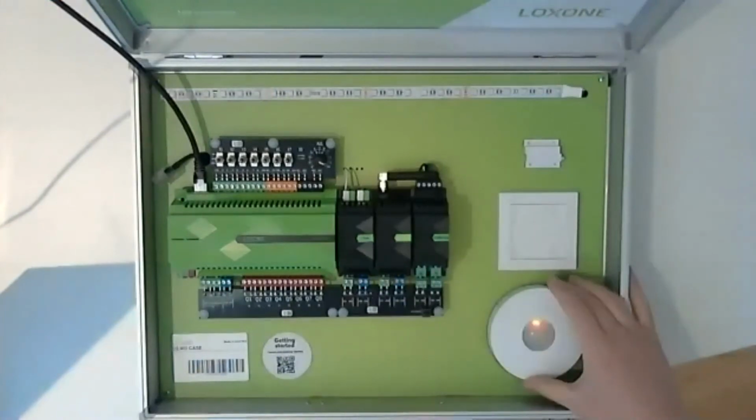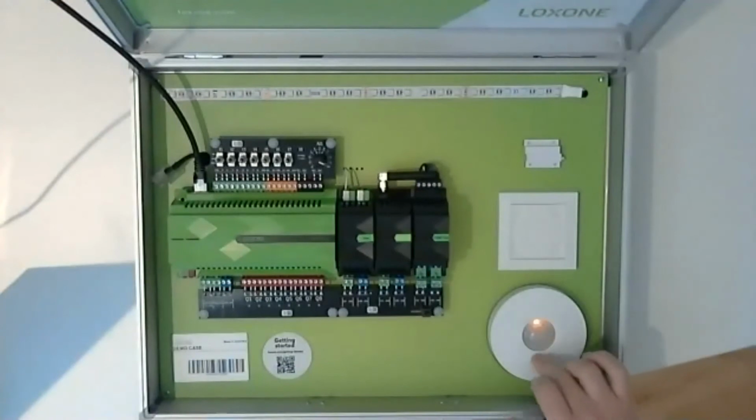For Air and Tree peripherals, again, they have different ways of identifying themselves. In fact, on the back of the touch switch, there is also a little LED as well. Again, orange means that it's healthy, but it's not connected to anything. It will stop flashing when it's connected, because obviously a flashing PIR, flashing motion sensor, isn't very nice. And again, it will flash red, green, amber rapidly when I've selected it in config.